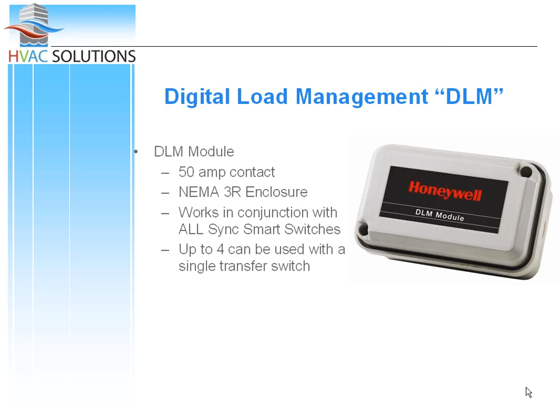Now, what's nice, on the AC1 or AC2 side, those are 24 volt connections. So what we're able to do is just drop out the Y1. So we're just running control wiring over to AC1 and AC2. And I will say rarely do I see where we need to shed 4 240-volt loads outside of the air conditioners. All right, so that's the DLM. You can use up to 4.